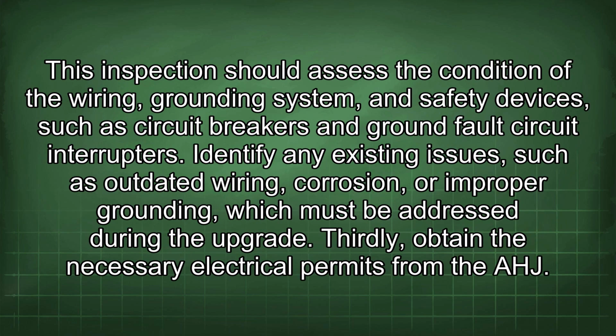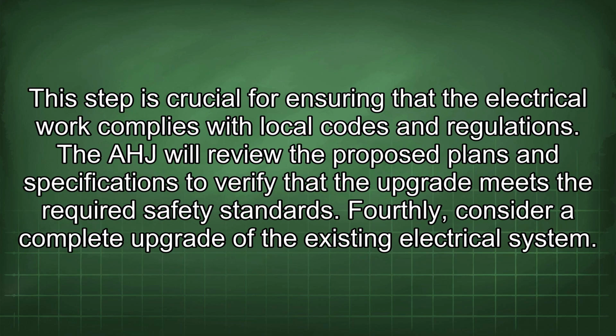This inspection should assess the condition of the wiring, grounding system, and safety devices, such as circuit breakers and ground fault circuit interrupters. Identify any existing issues, such as outdated wiring, corrosion, or improper grounding, which must be addressed during the upgrade. Thirdly, obtain the necessary electrical permits from the AHJ. This step is crucial for ensuring that the electrical work complies with local codes and regulations. The AHJ will review the proposed plans and specifications to verify that the upgrade meets the required safety standards.